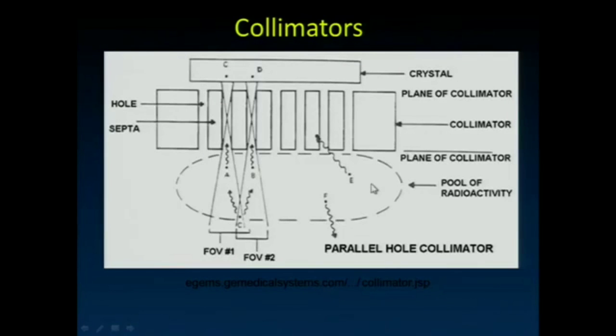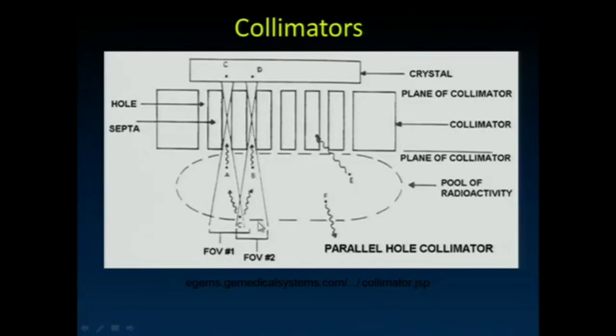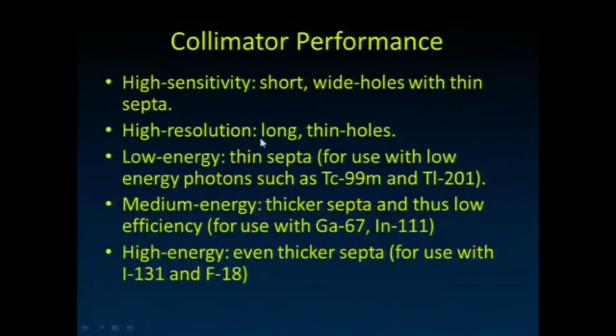The further you get from the nuclear medicine gamma camera, the poorer your resolution becomes. Each hole in the collimator samples a wider area the further away you get, and that wider field of view determines the resolution at a particular depth. It's therefore very important to get the object of interest as close as possible to the gamma camera to maintain high resolution.